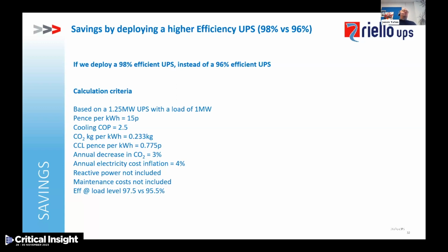We've used a climate change levy of 0.775, an annual decrease in CO2 production of 3%, which we can vary, and an annual electricity cost inflation of 4%. I've not included reactive power because this is typically showing two new UPSs, which would have a very good input power factor anyway. But if you were replacing an older machine, like an old 12 pulse, then reactive power would come into it. I've not included maintenance costs because I'll look at that shortly.